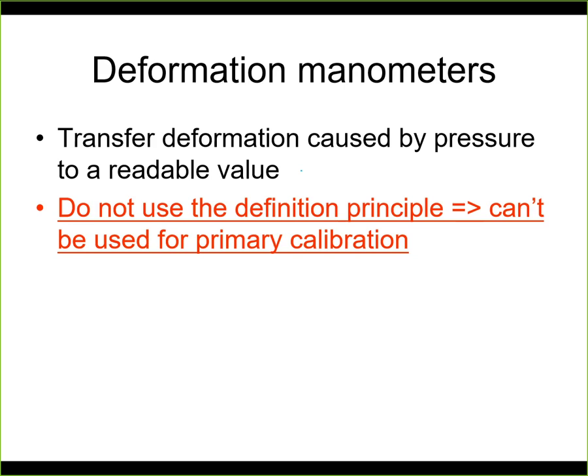Deformation sensors are typically used in industrial systems simply because the calibration instruments for pressure are very sensitive to vibrations, to dirt and so on. So they are used in labs to calibrate the instruments.